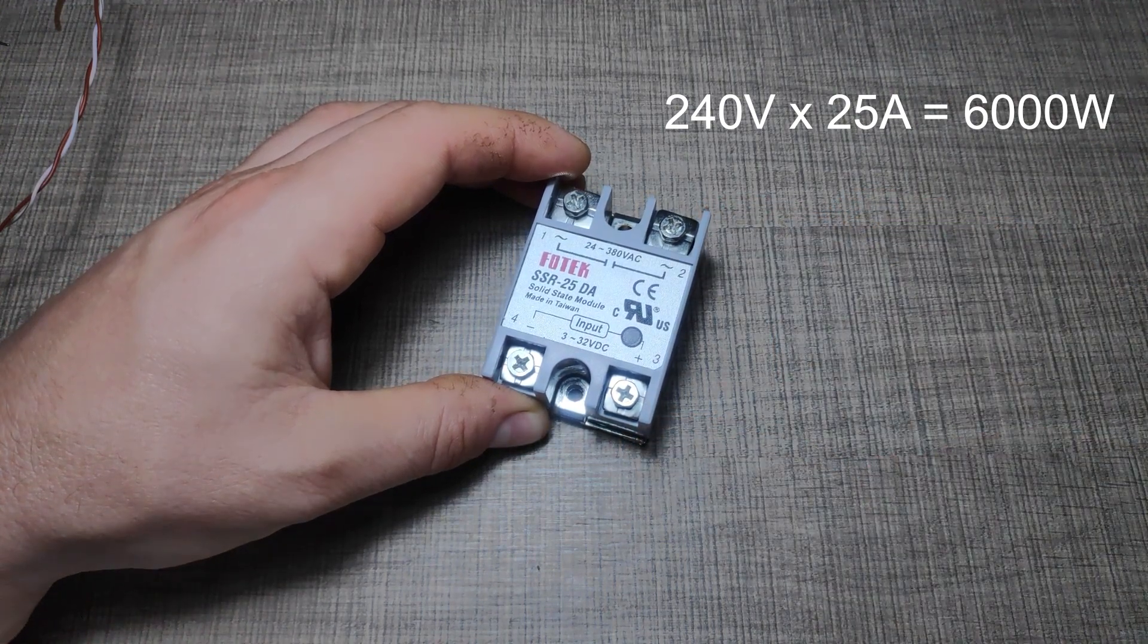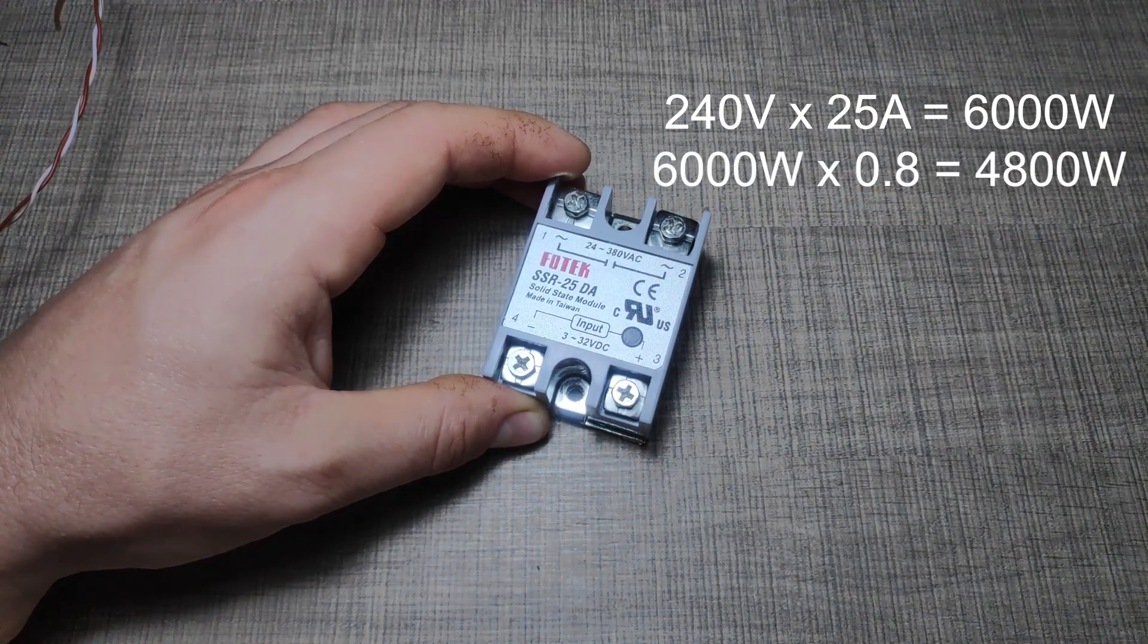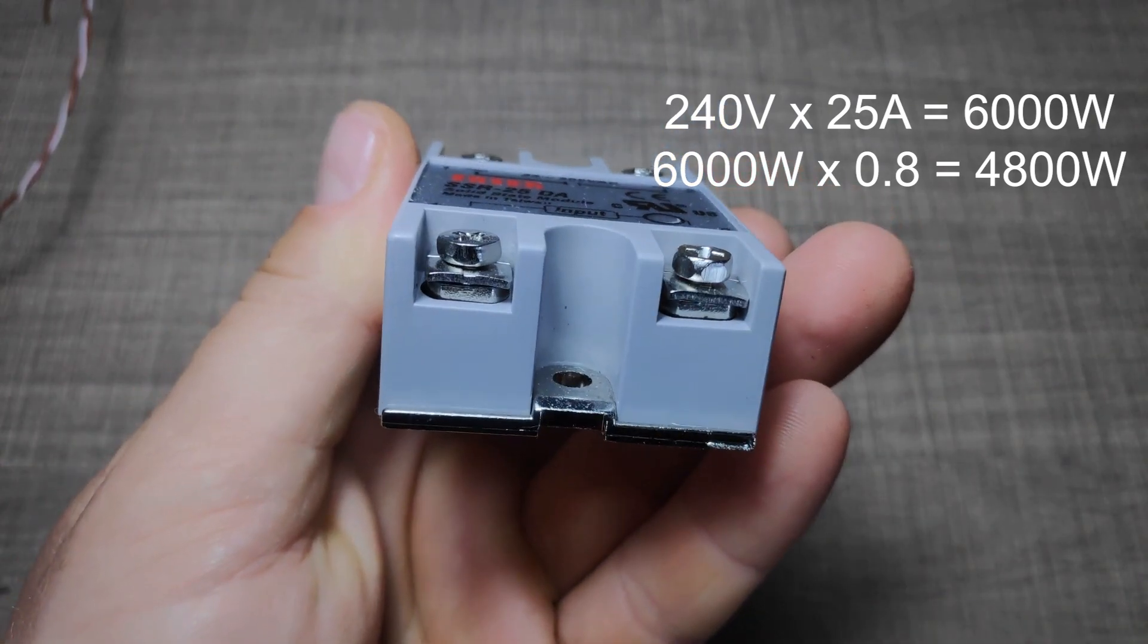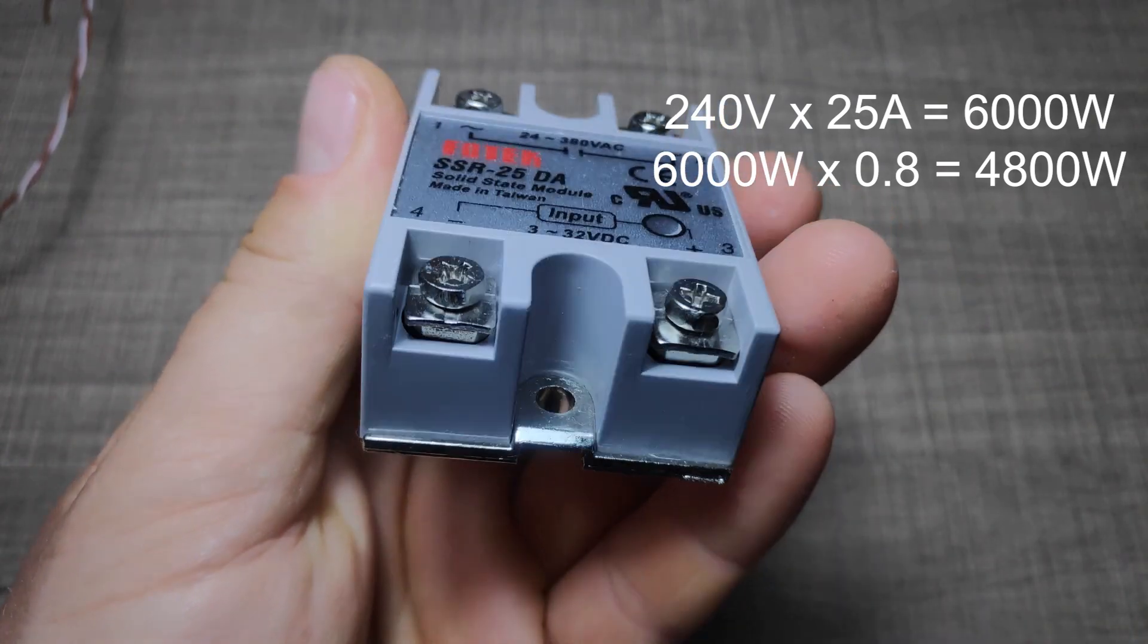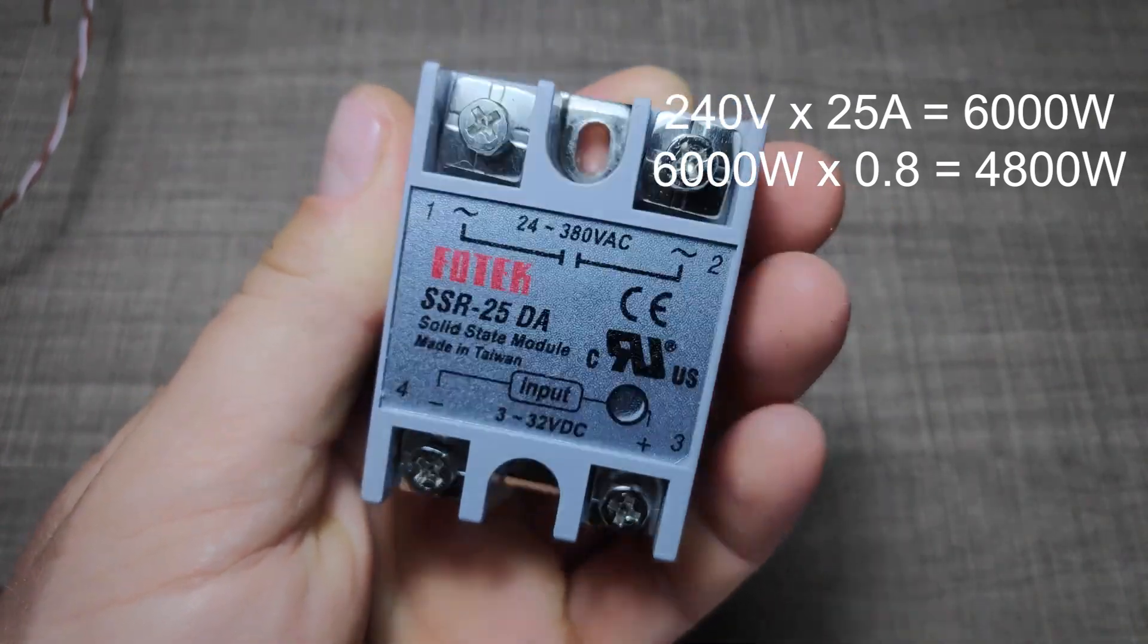To protect your SSR, it's recommended that you never run it above 80% of its maximum, so this brings us down to 4.8kW.